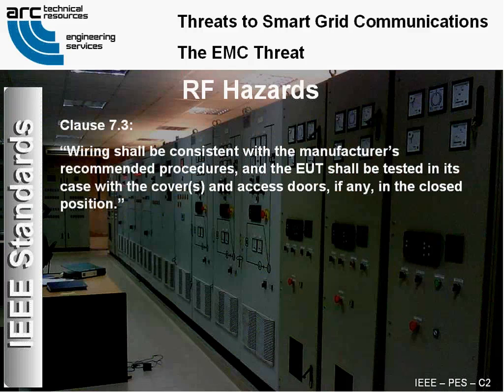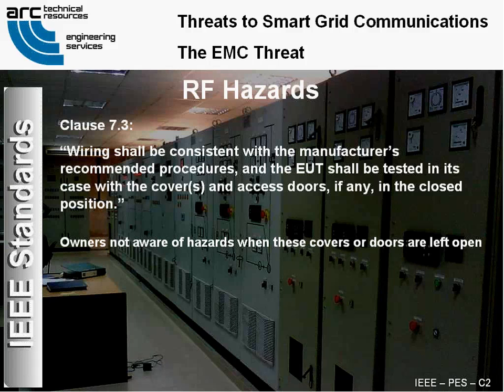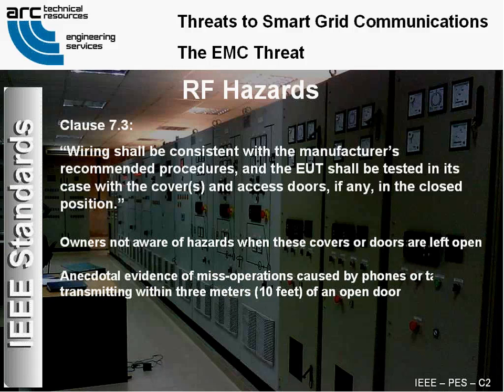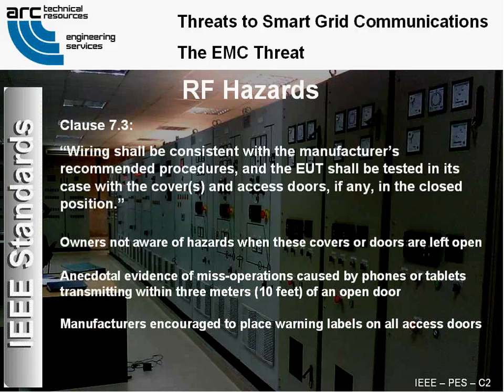RF hazards. Clause 7.3 of the draft states that wiring shall be consistent with the manufacturer's recommended procedures, and the EUT shall be tested in its case with the covers and access doors in the closed position. Owners of installed communications networking devices may not be aware of the hazards that exist when these covers or doors are left open. There is anecdotal evidence of misoperations caused by cell phones or tablets transmitting within 3 meters of an open door on a communication networking device. Thus, manufacturers are encouraged to place warning labels on all the access doors and covers, alerting the user that a misoperation may occur if the doors are left open, and that phones and tablets should not be allowed closer than 3 meters from the equipment.